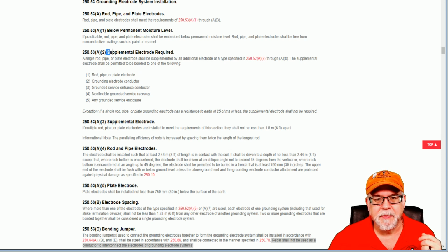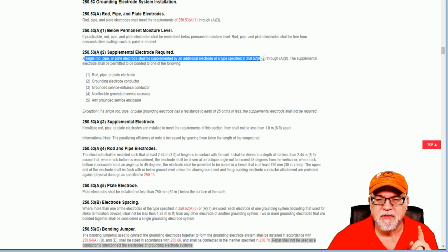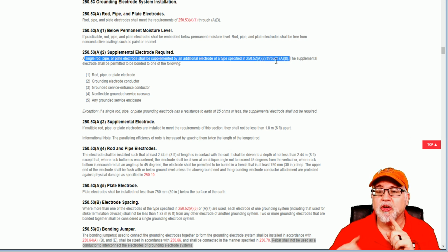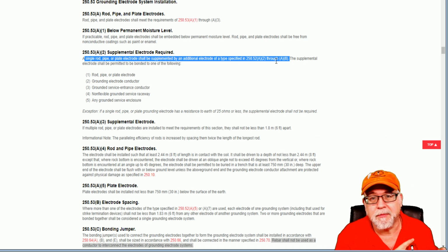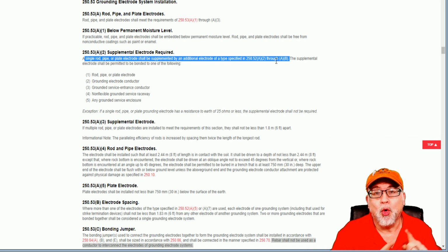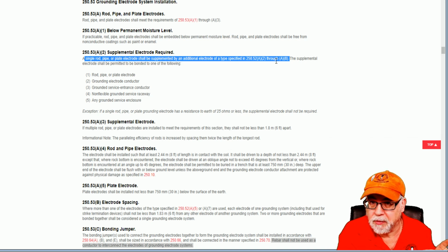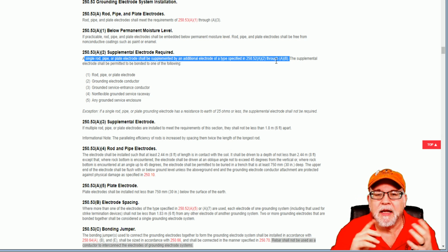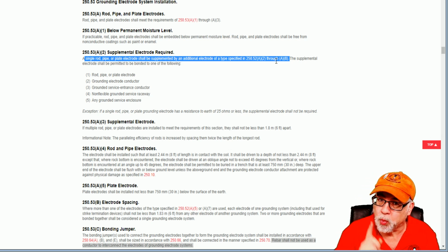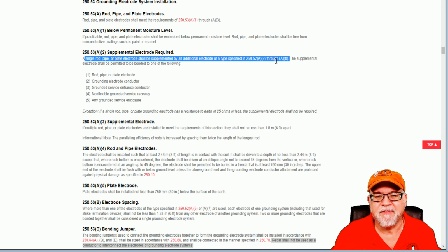And then, of course, here's what we were talking about in our question. This is a supplemental electrode requirement. Notice it says a single rod, pipe, or plate electrode shall be supplemented by another electrode of the type specified in 250.52(A)(2) through (A)(8). Now, you notice (A)(1) is not here because you have to supplement a water pipe ground anyway, and you obviously can't supplement a single rod, pipe, or plate with the water pipe ground that could be removed in the future anyway. So you wouldn't do that, okay? So if you're going to do a single rod, pipe, or plate, and all you want to do is put one in, then you have to supplement it unless you meet the exception.